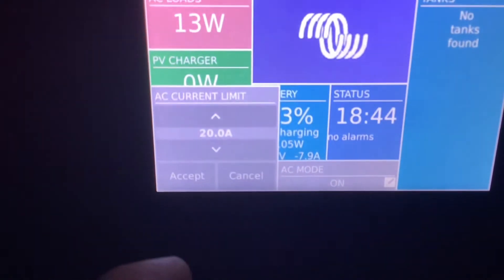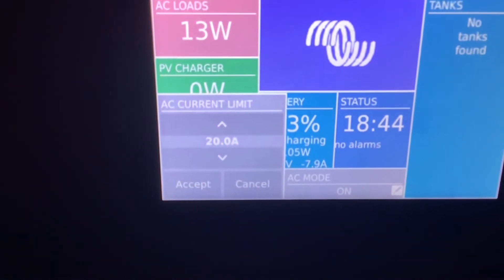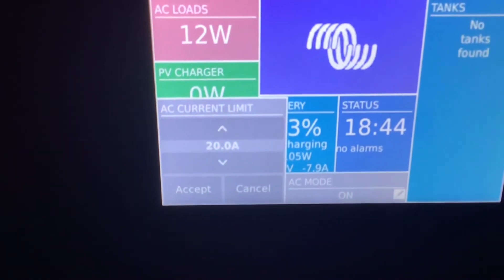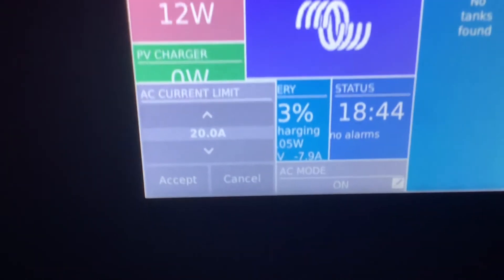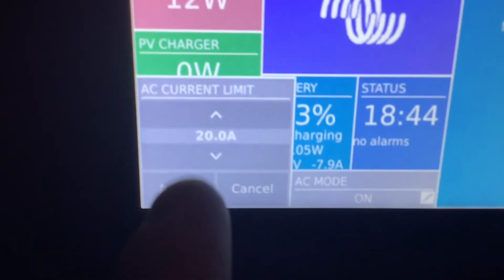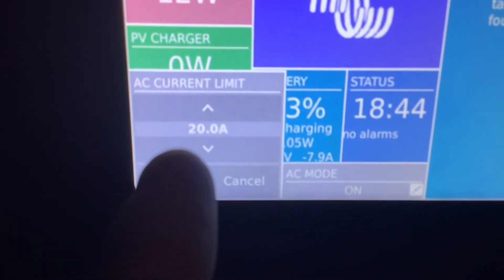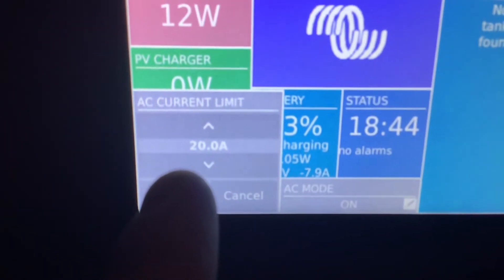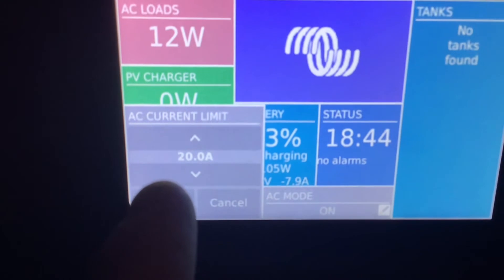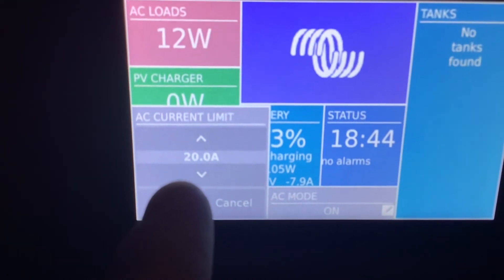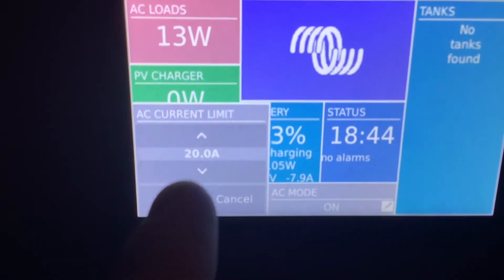When on shore power or generator power, the inverter prioritizes the AC loads and sends power to AC loads first, and anything that's left over up to this limit will be used to charge the battery.